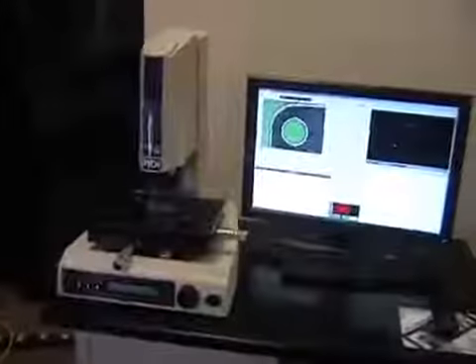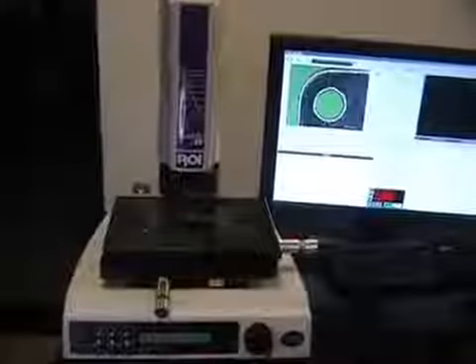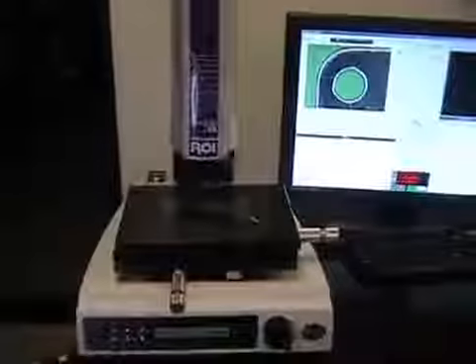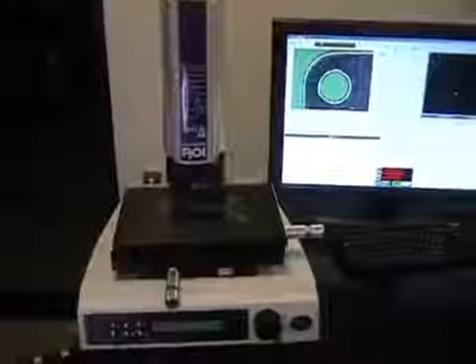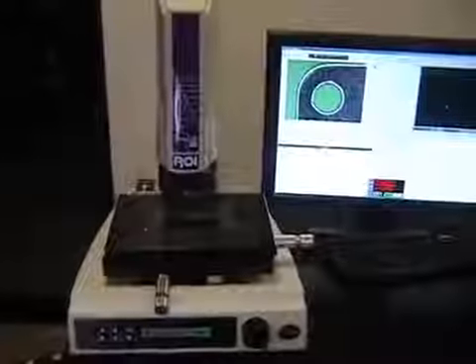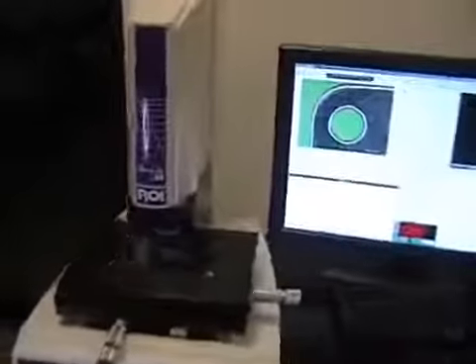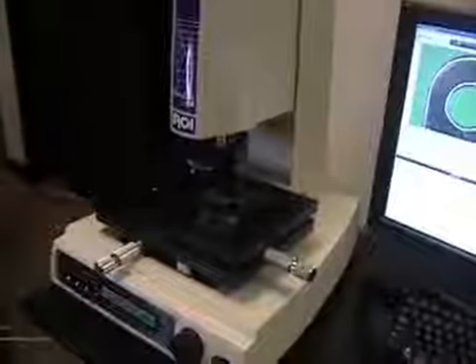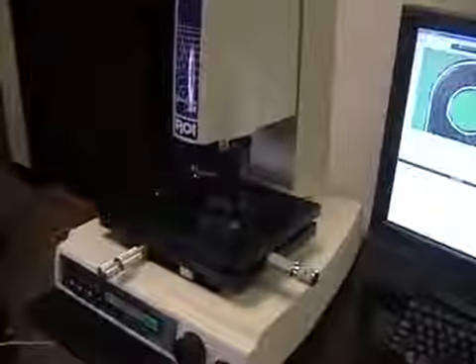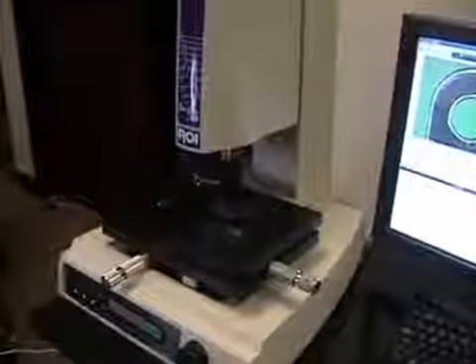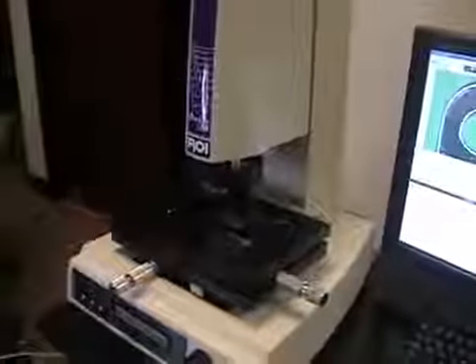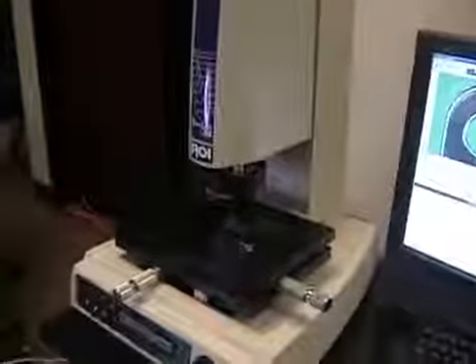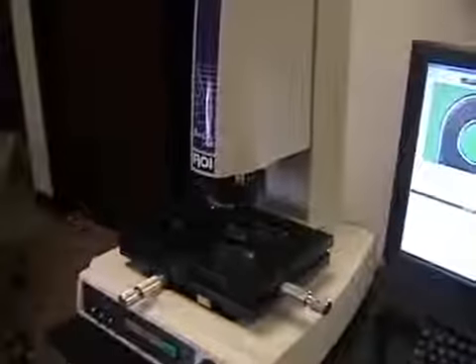First of all, we have the Starlight GX system itself: the hardware, optics, lighting, and controls. The Starlight GX is a 6 inch by 3 inch by 5 inch measurement volume. It uses a 6.5x zoom lens, which enables on-screen magnification of approximately 33x to 175x. There are standard light systems built in.